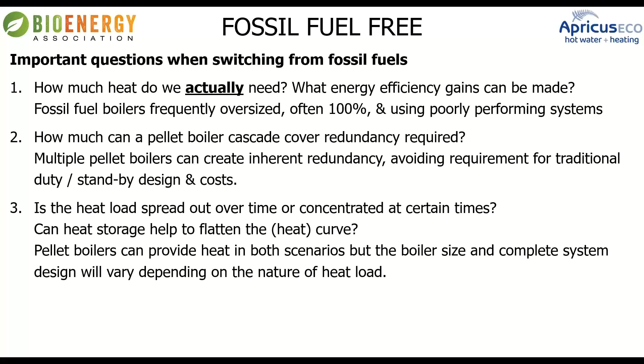Pellet boilers can definitely do both scenarios—very peaky or flattened—but the boiler size and complete system design will vary quite a lot depending on the nature of the load. In general, if we can flatten off the curve, it's going to be cheaper to install and more efficient to run, and that's across the board.